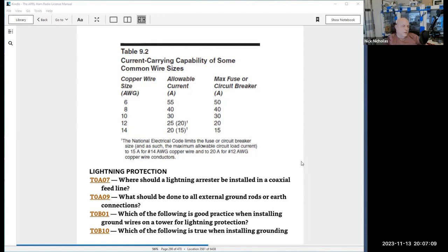Now, lightning arrestors are mandatory under Part 810 of the National Electric Code. And nowadays, feeding into your house just before the coax or feed line enters the house is where the lightning arrestor should be. It should be grounded to ground at the nearest point where the building itself's grounding point is. Usually right outside where the box is on the inside for your fuses or circuit breakers. All grounds should be kept as short as possible, as direct as possible, with as few arcs or bends. If you have to bend around something or make a bend, they should be very broad, rounded bends. This is to ensure that if there is a lightning strike, it can travel to ground and not get trapped by the physics of the mechanics of the electrical path.